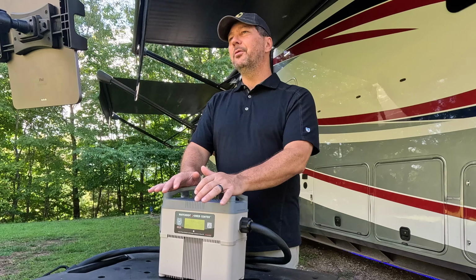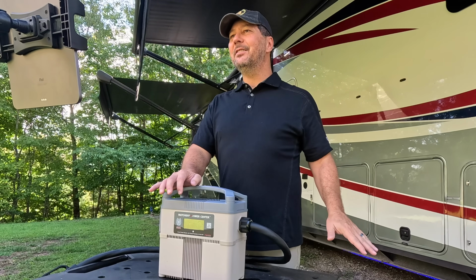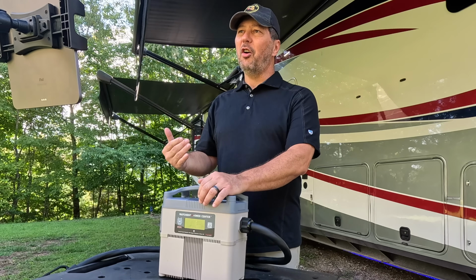Like the old Watchdog we had, this protects against high and low voltages with emergency power off. But that range is much greater on the low end because the Autoformer is built into this system. The Watchdog has a range of about 104 to 132 volts where it cuts power on either side, but this goes as low as 96 volts up to 132. That's because the Autoformer is built in. When voltage drops below around 112 to 113 volts, it gives about a 9% boost. That lets your input voltage from the park go down to 96 volts before it has to trigger the EPO and shut off power to protect your RV.